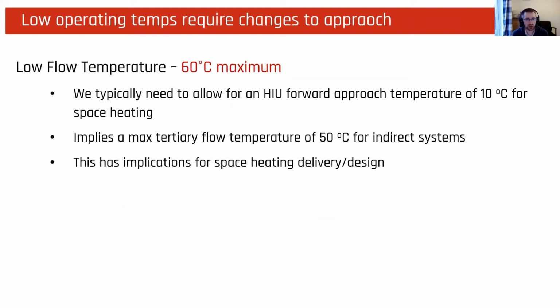So in new build, the goal is 60 degrees, the maximum we really want to be distributing at for heat pump systems. And when we've got twin plate HIUs delivering instantaneous hot water and space heating, we really want a 10-degree forward approach from what we're delivering to our HIU from our heat network to what we're delivering on the dwelling side, particularly with the space heating systems, which puts a threshold for 60 of 50 degrees on our dwelling systems. And that has quite big implications for space heating systems.